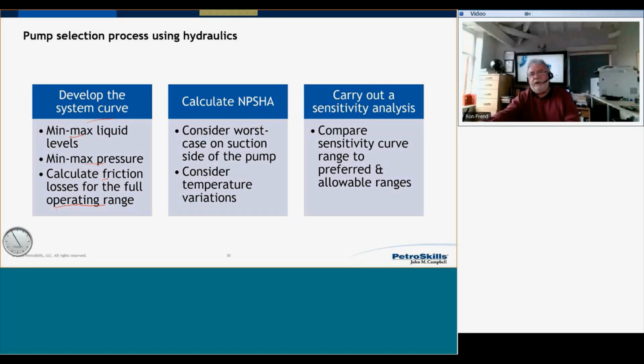For your NPSH, consider the worst case of suction on the pump. Think of the suction side. That's where you're going to get cavitation. And don't forget about temperature, because remember, this thing about NPSH is not just pressure. It's that pressure-temperature combination.